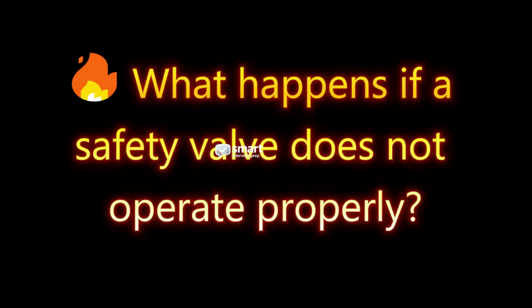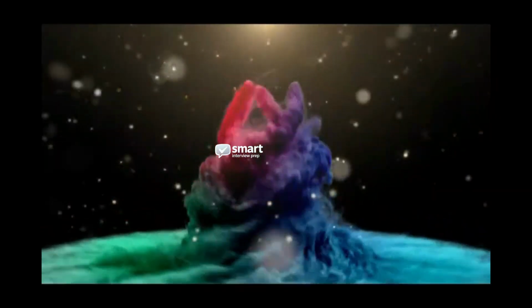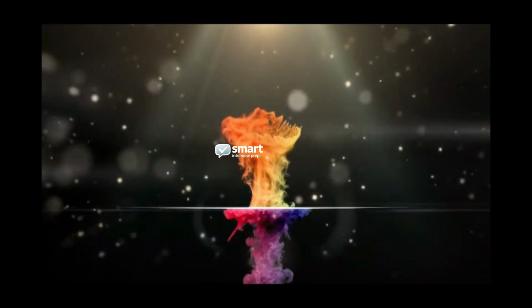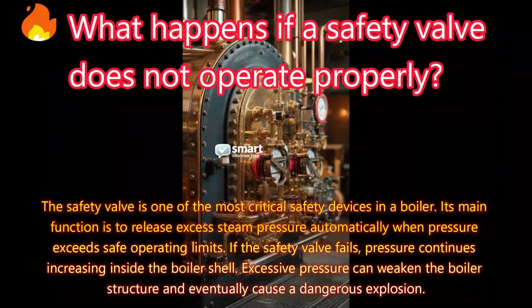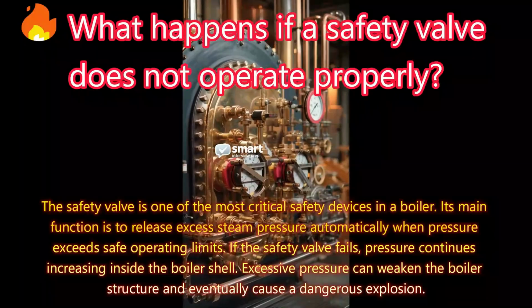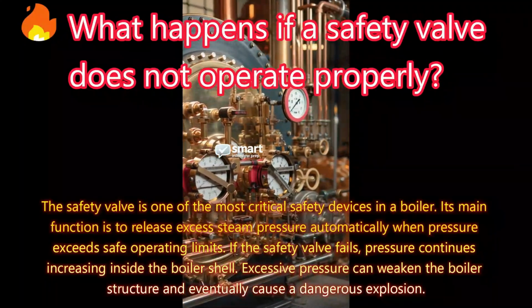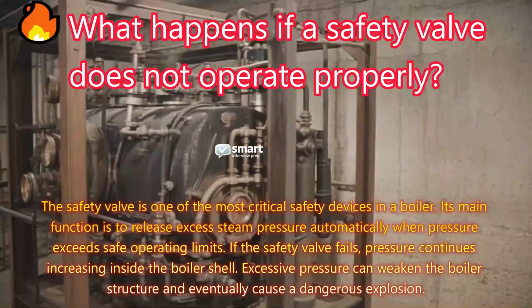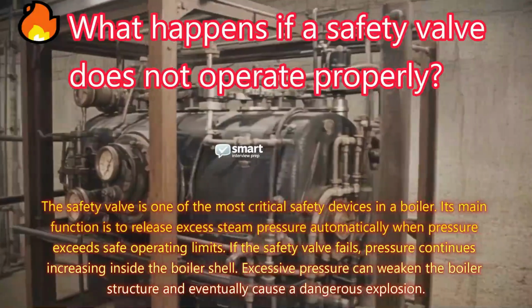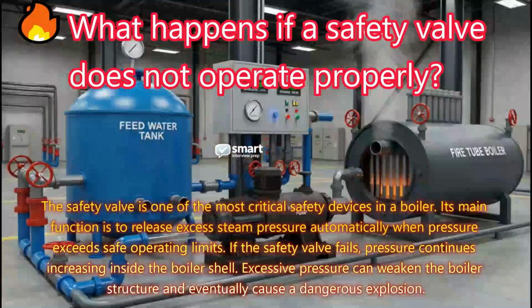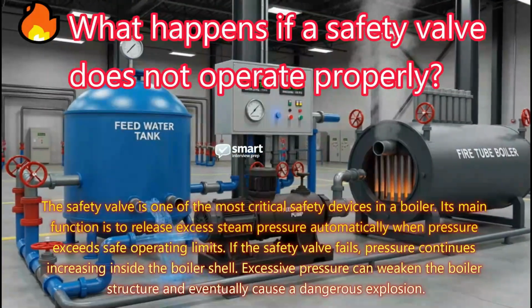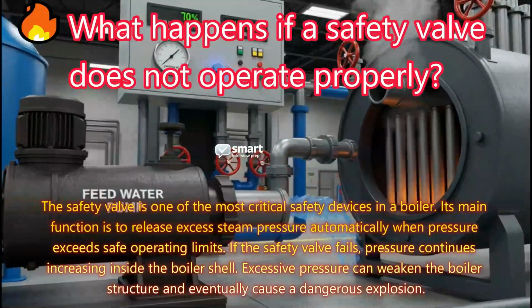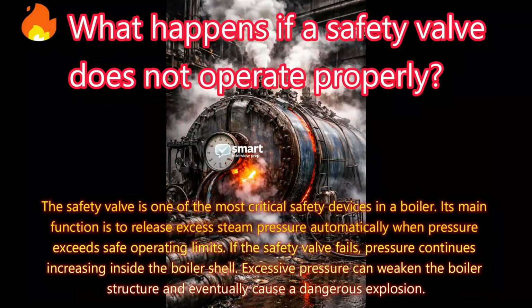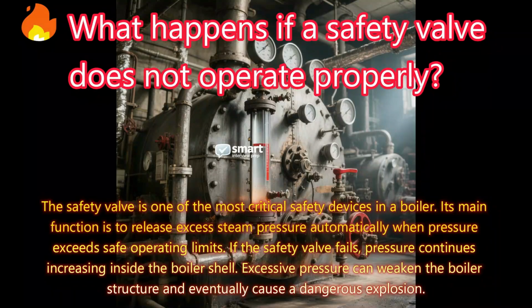What happens if a safety valve does not operate properly? Answer. The safety valve is one of the most critical safety devices in a boiler. Its main function is to release excess steam pressure automatically when pressure exceeds safe operating limits. If the safety valve fails, pressure continues increasing inside the boiler shell. Excessive pressure can weaken the boiler structure and eventually cause a dangerous explosion.